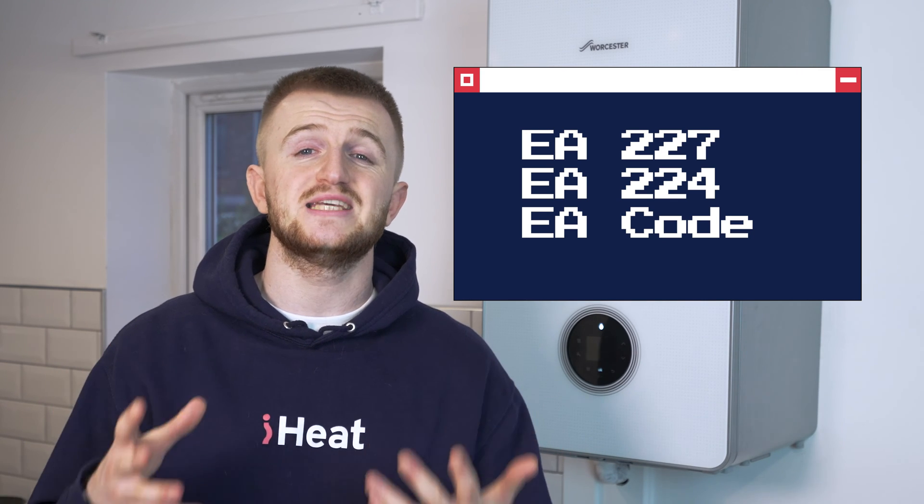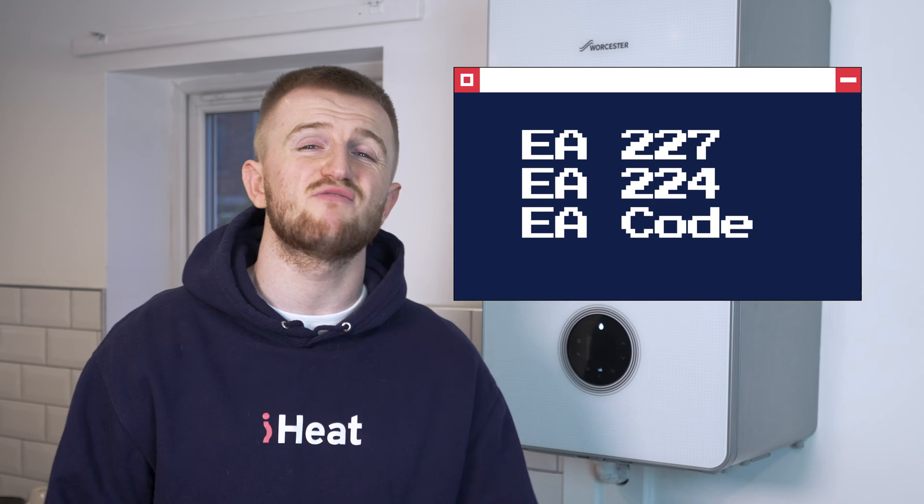Before we dive into the details of each error code, try resetting the boiler to wipe any error code. This can often fix the issue and save you on that engineer call-out fee. With the Worcester Bosch range, just hold the up and down arrows until it resets. If that doesn't work or your boiler doesn't have those buttons, just turn the fuse off, wait a few seconds, turn it back on and your boiler will have reset. If the error code still persists, carry on with this video.